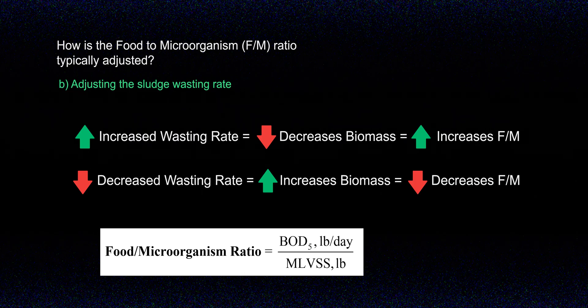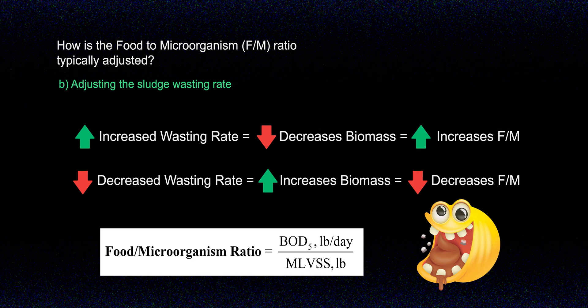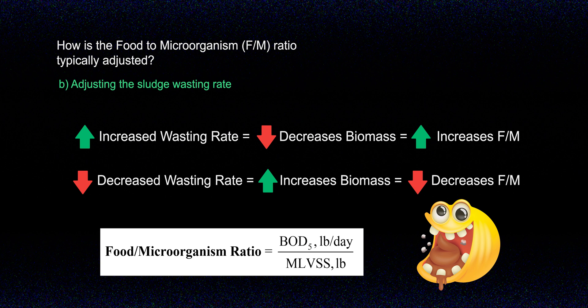It's important to understand that just because you increase or decrease your wasting rate, you may not get the results you want. Since you don't usually have control over what comes into your plant, you want to aim for staying within a range that works for your system rather than chasing a specific ratio. As a rule of thumb, you should not change your wasting rates more than 10 to 20 percent per day. Efficient and effective wastewater treatment is a moving target — make incremental adjustments and stay within a range, because what works one week may not work exactly the same the next.